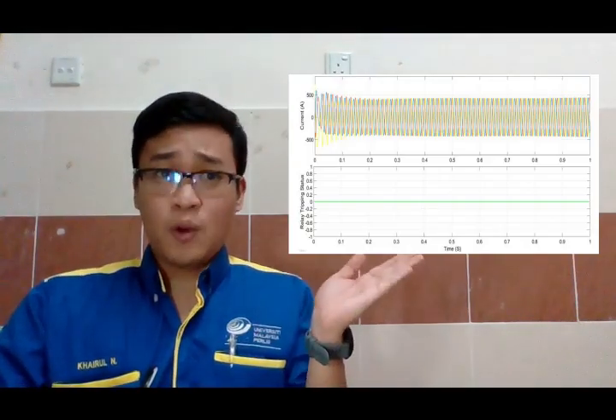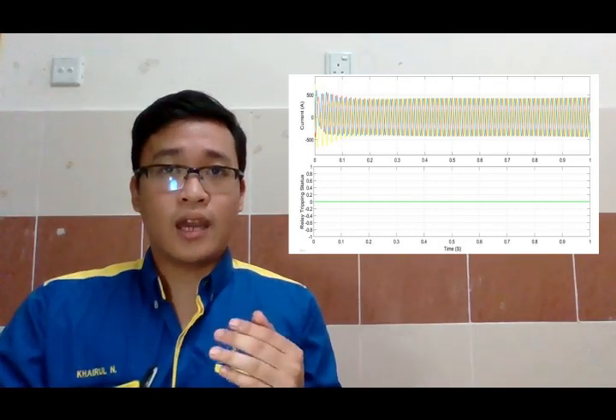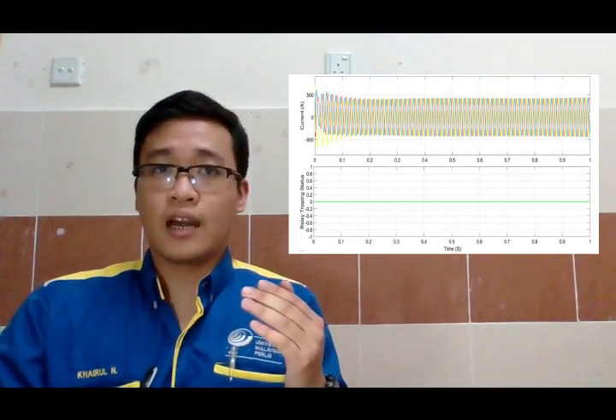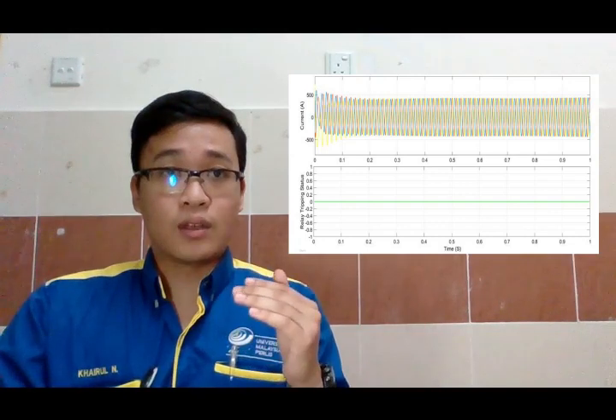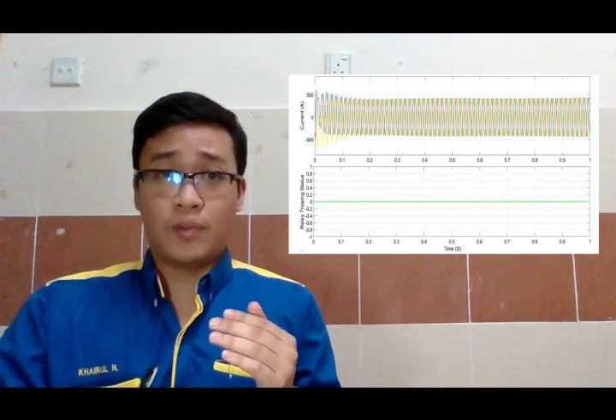Initially, the evaluation is conducted under normal operating conditions. In the absence of any faults, as anticipated, the relay does not identify any unusual events within the network, and the logic implemented in the FPGA-based relay remains at zero throughout the entire simulation, as depicted in this graph, which shows the wind farm behavior and performance, where the upper graph is the wind farm current and the bottom graph is the trip signal from the FPGA DDPR.